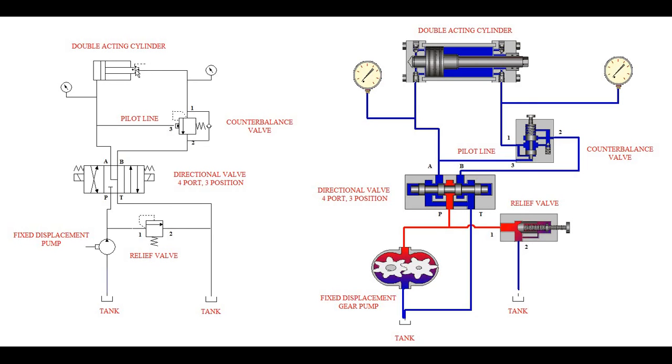We don't want this cylinder to run away from us when we're extending it, because that could make the pump cavitate, that could make us get air in the system. More importantly, we want to have precise control of the load. We want to be able to modulate it properly and safely.